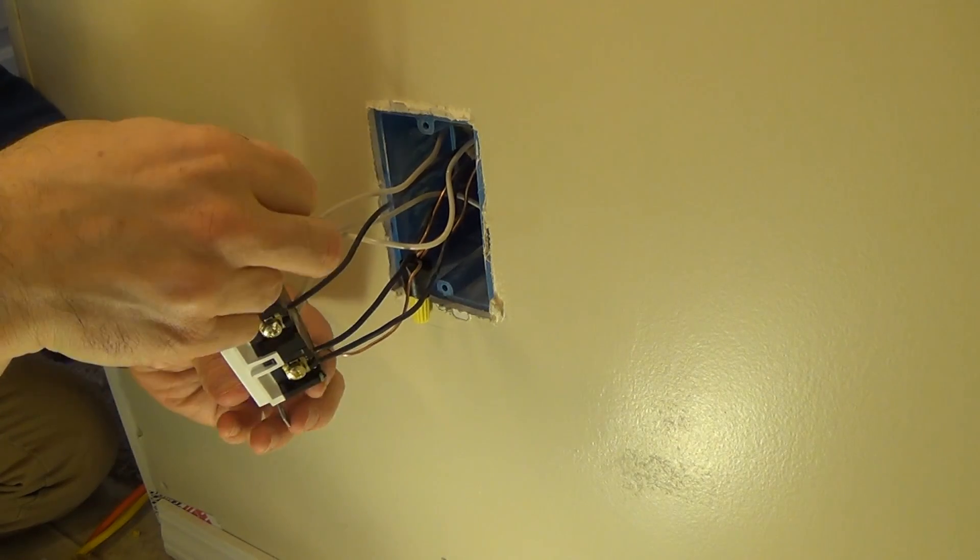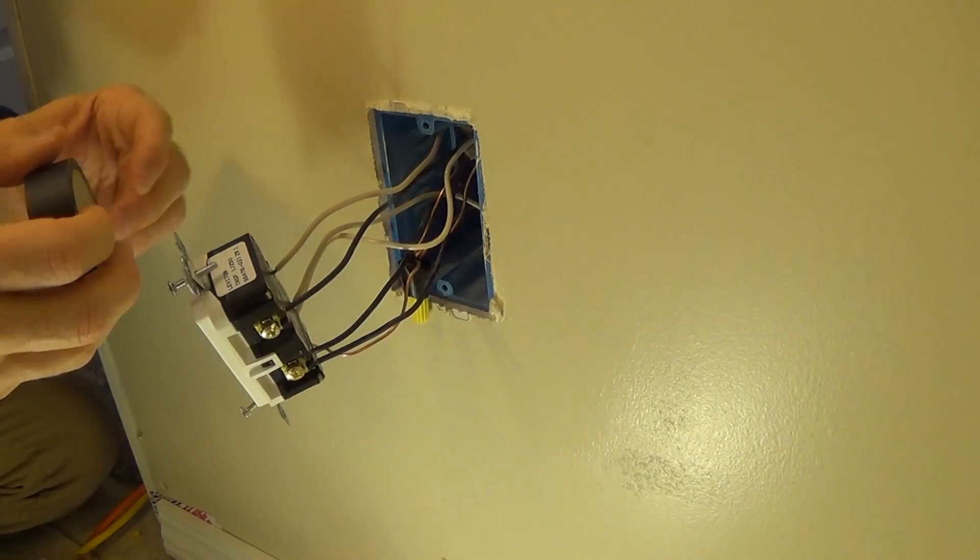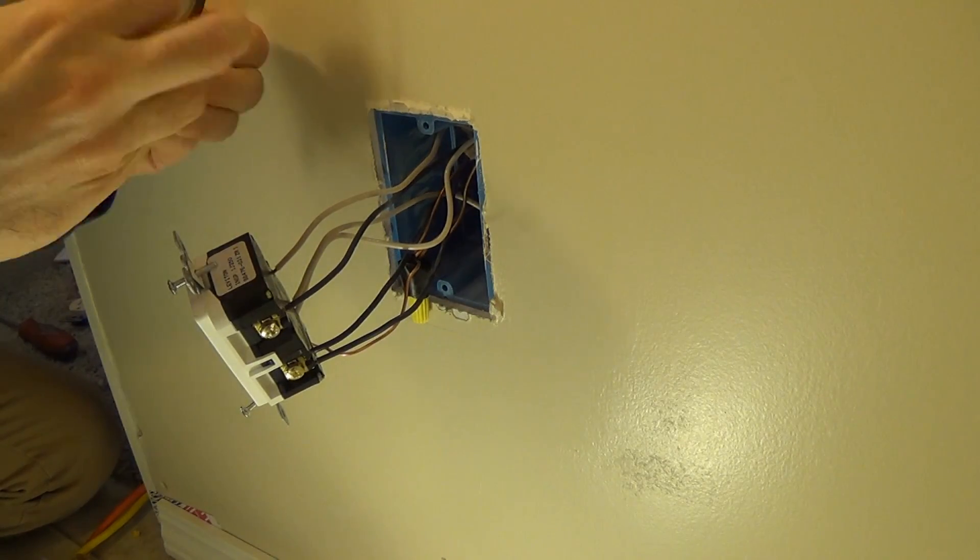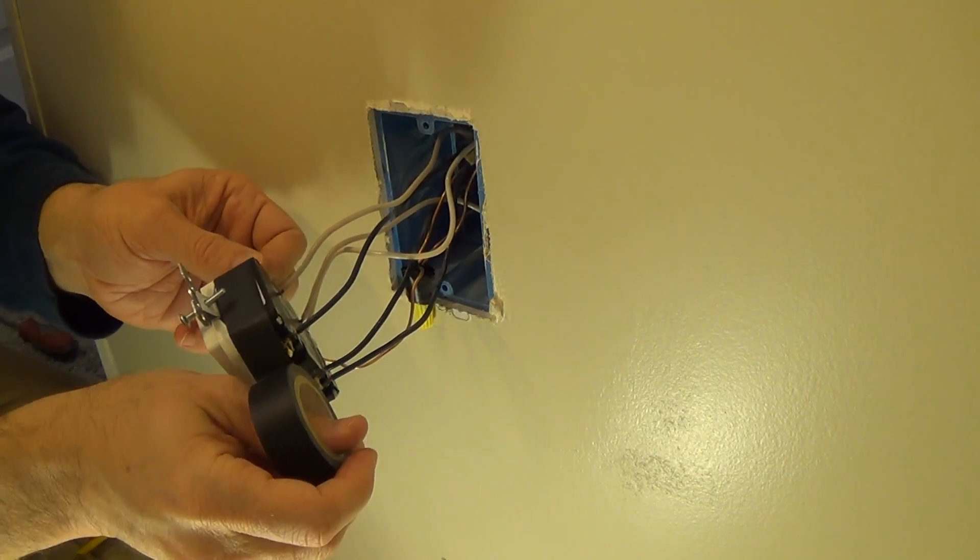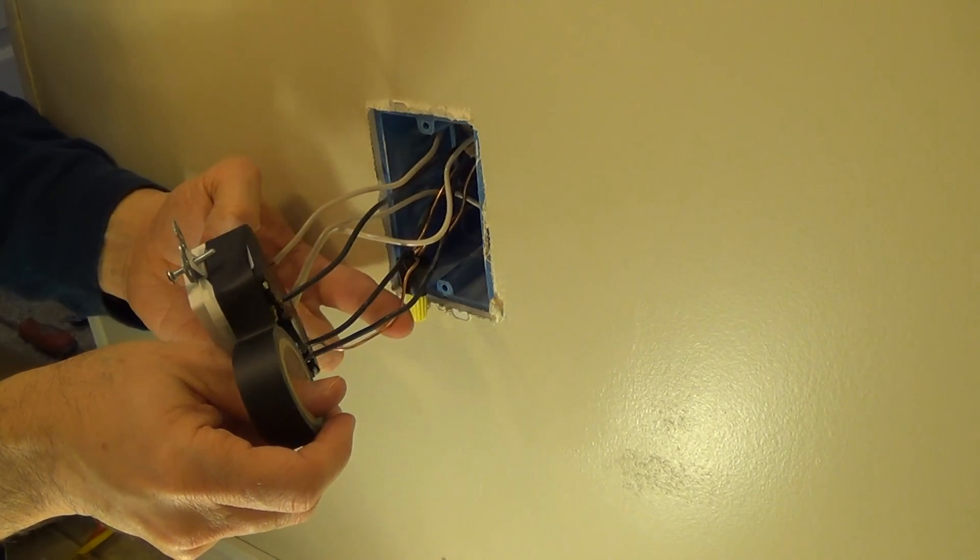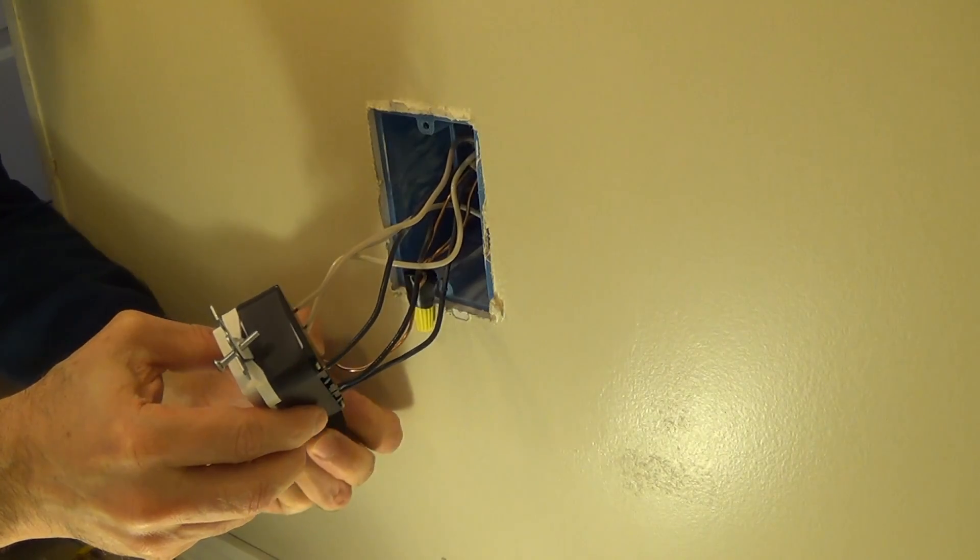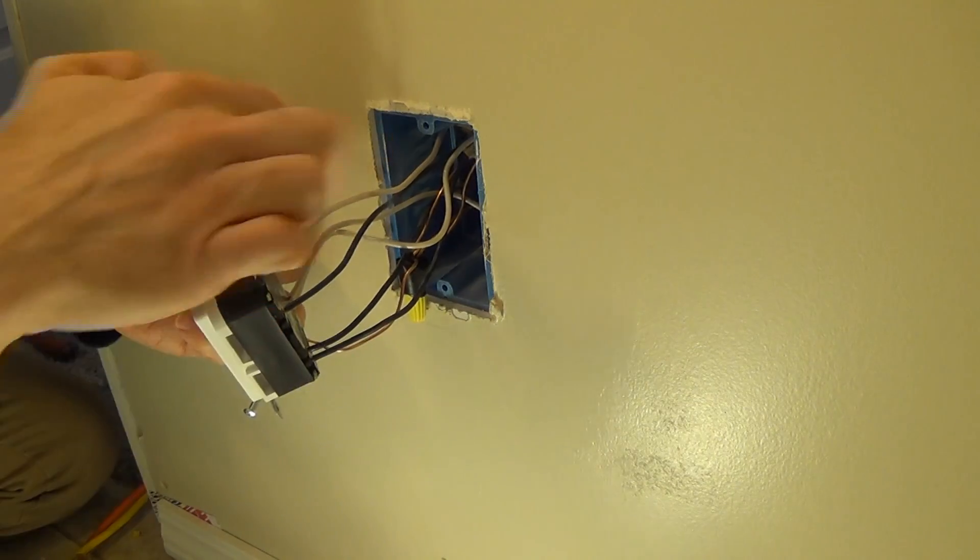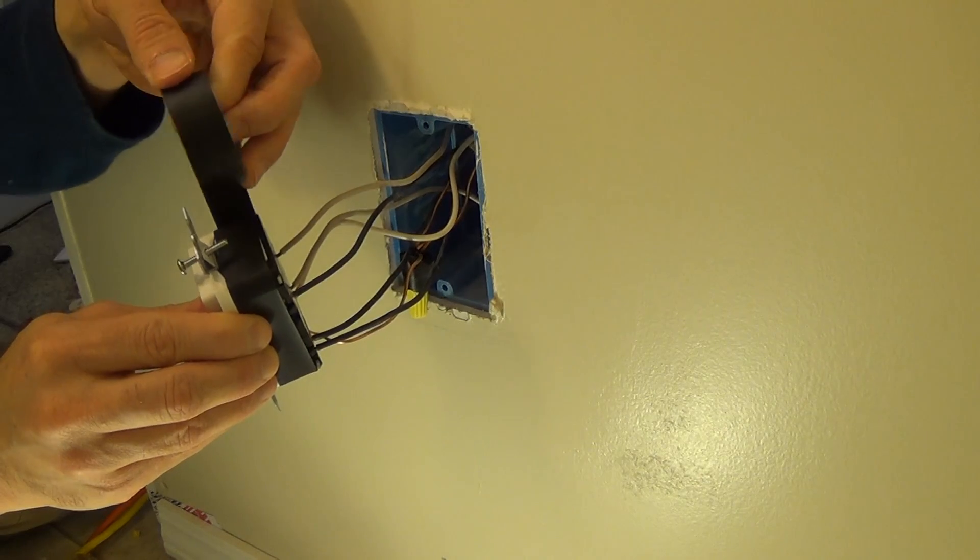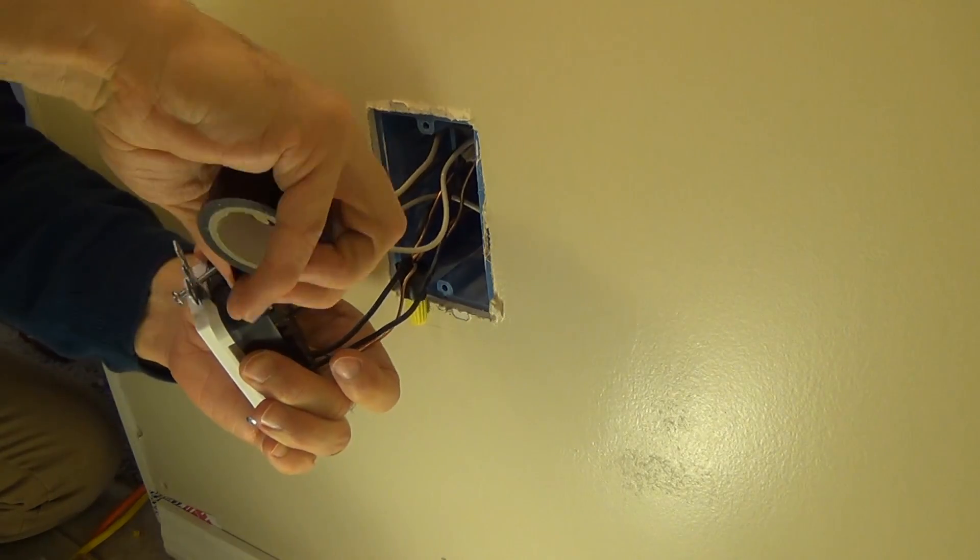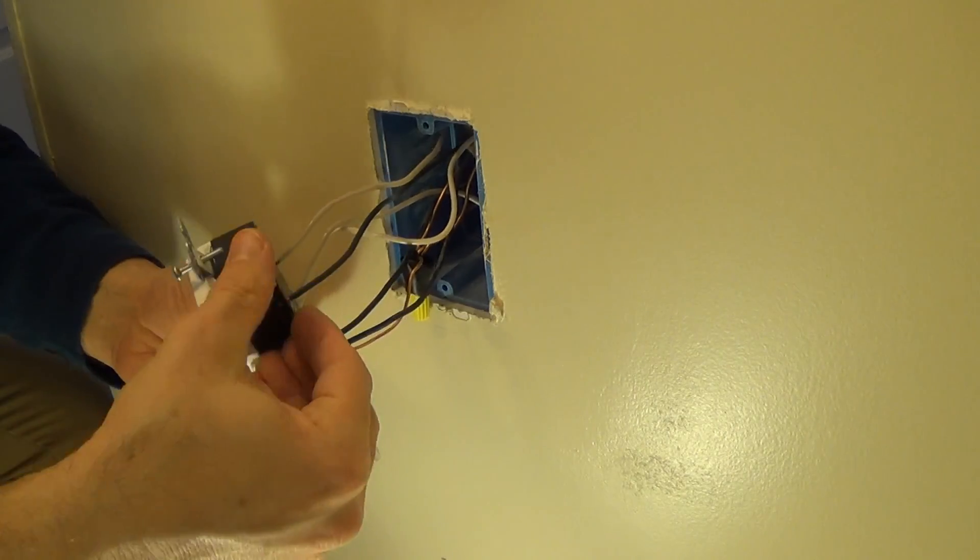So what I like to do at this point is I actually like taking some electrical tape and I actually like to just kind of cover these terminals. One reason: it helps protect these terminals from contact because these grounding wires are exposed and sometimes if you're not careful they could shift and you can move them around and actually touch these terminals, and that's not good. So I always like to stick in some electrical tape to kind of cover those.